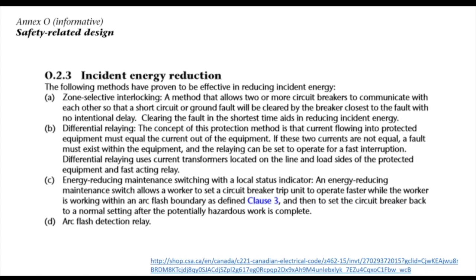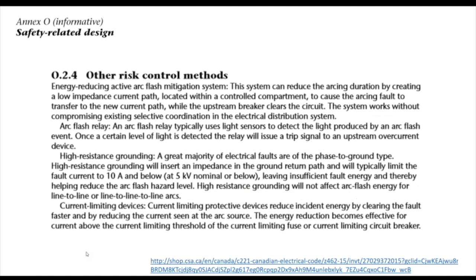Energy reducing maintenance switching with a local status indicator is a wonderful way to reduce incident energies. And by the speed, you can put it in a maintenance position on the outside chance there is a mistake. We're going to touch on human performance a little bit in a few minutes. People do make mistakes. They do have bad days, and certainly a maintenance switch can reduce the severity and the likelihood of an incident. So it's good. Same with arc flash relays, looking at light.